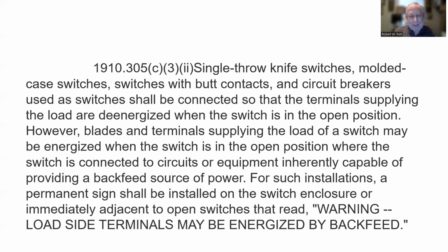Switches with butt contact and circuit breakers used as switches shall be connected so that the terminals supplying the load are de-energized when the switch is in the open position. That makes sense. However, blades and terminals supplying the load of a switch may be energized when the switch is in the open position, where the switch is connected to circuits or equipment inherently capable of providing a backfeed source of power. For such installations, a permanent sign shall be installed on the switch enclosure or immediately adjacent to open switches that reads, warning, load side terminals may be energized by backfeed.